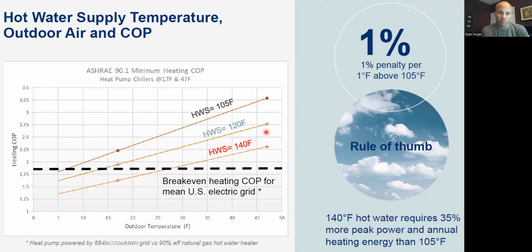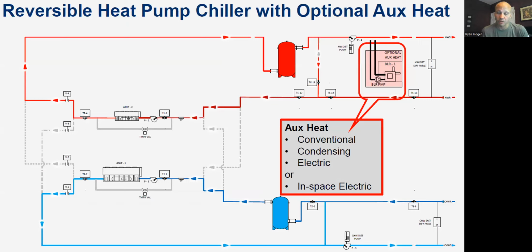If I ask for warmer water, I'm going to be making fewer BTUs, right? Indicated over here, and I'm going to be making them less efficiently, right? It costs less money to make 105-degree hot water than it does to make 140-degree hot water. That's kind of intuitive, I think. So in these cases, I'll be losing efficiency, and at some point down here, it's going to be cheaper or smarter from the COP standpoint to run my boiler. Cheaper would depend on the cost of my two fuels, and that'd be a different mathematical calculation. So in other words, design for lower water temps, which means put in bigger hot water coils and or bigger radiators or whatever you have, bigger heat exchanger for domestic water, etc.